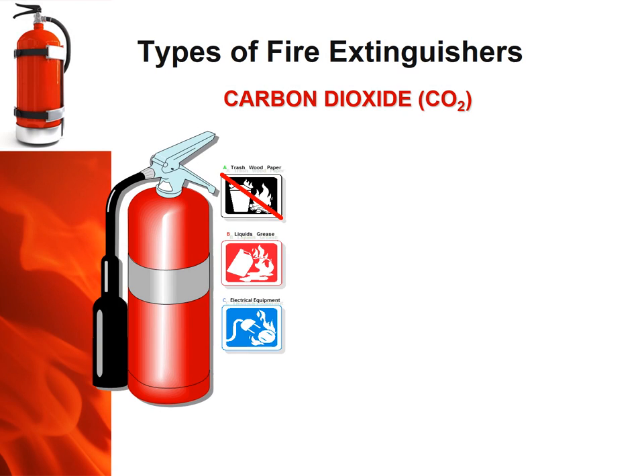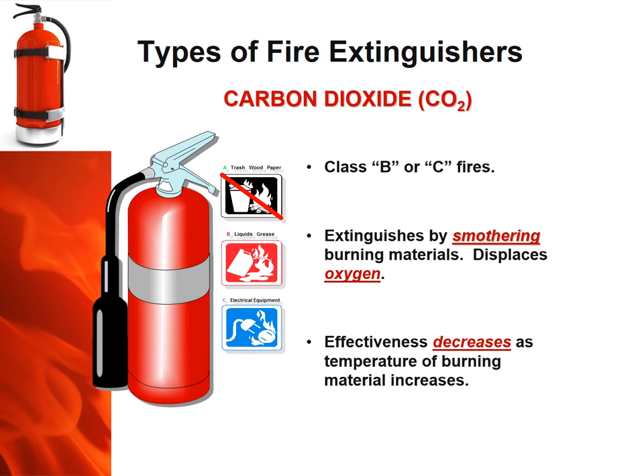The carbon dioxide fire extinguisher, which is sometimes filled with halon, is used around electrical components — we use them in our computer room. They have no pressure gauge; their capacity is verified by weight. These extinguishers extinguish fires by smothering the burning materials and displacing the oxygen, thereby killing the fire. Their maximum effective range is just 3 to 8 feet.